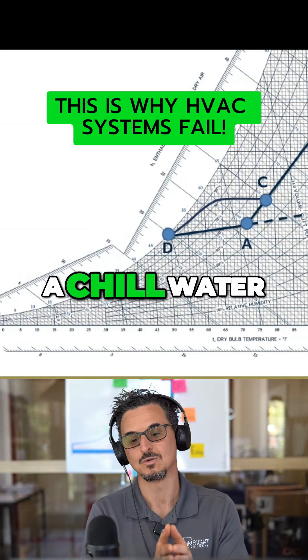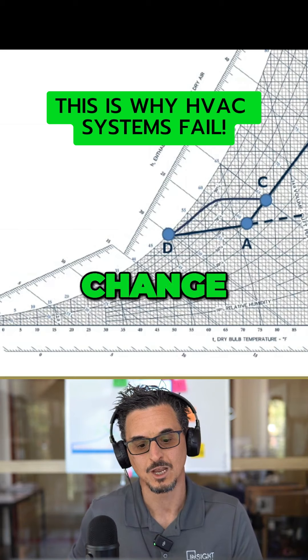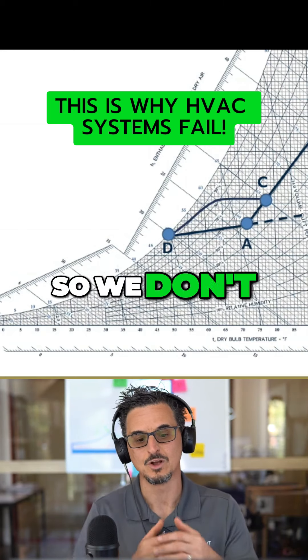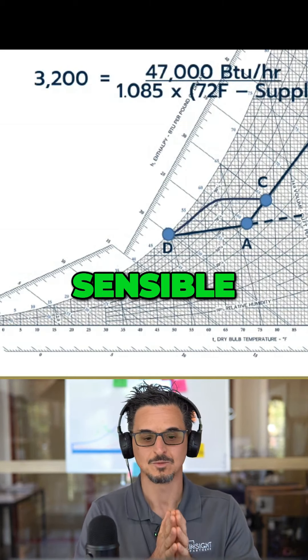The only other thing you could do is change the supply air temperature. So in our example here, we're using a chilled water coil with a modulating valve, three-way valve or whatever. We're going to change the leaving air temperature so we don't over-cool the space at part load condition. How do we know what temperature to provide? Well, we go back to our sensible heat equation.